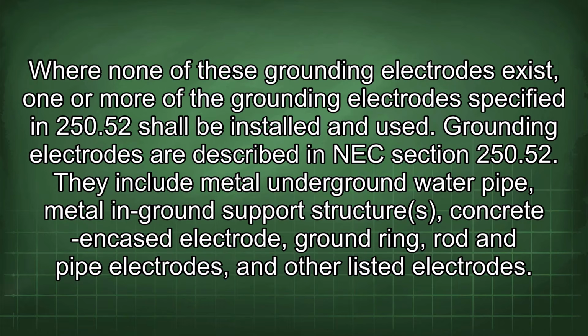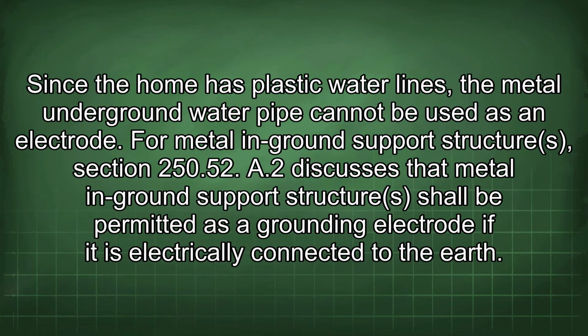They include metal underground water pipe, metal in-ground support structures, concrete encased electrode, ground ring, rod and pipe electrodes, and other listed electrodes. Since the home has plastic water lines, the metal underground water pipe cannot be used as an electrode.